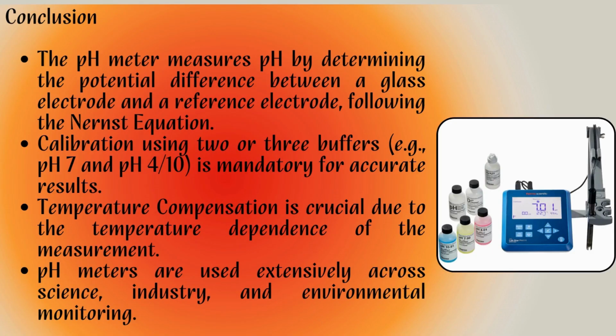To conclude, the pH meter is an indispensable tool. It works by measuring the electrical potential difference between the glass and reference electrodes, a relationship governed by the Nernst equation. Remember that calibration with standard buffers is mandatory for accurate results, and automatic temperature compensation is crucial due to temperature sensitivity. Whether in a research lab or water treatment plant, the pH meter plays a vital role in ensuring quality, safety, and scientific precision.